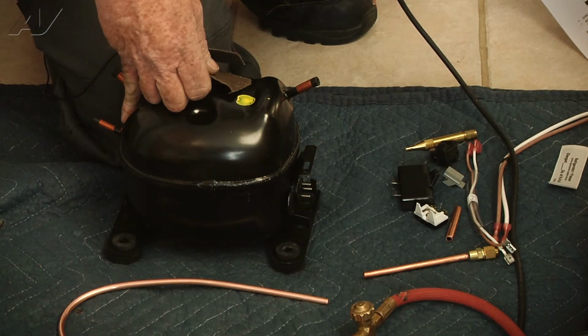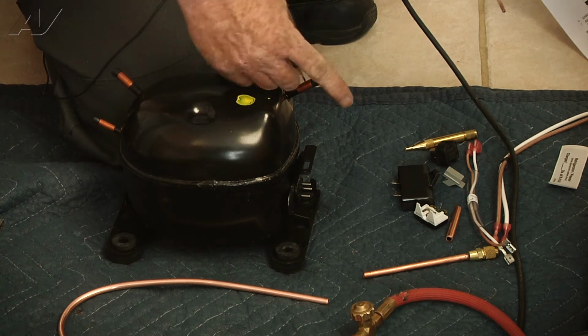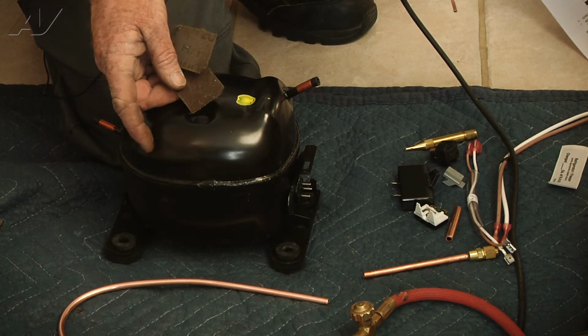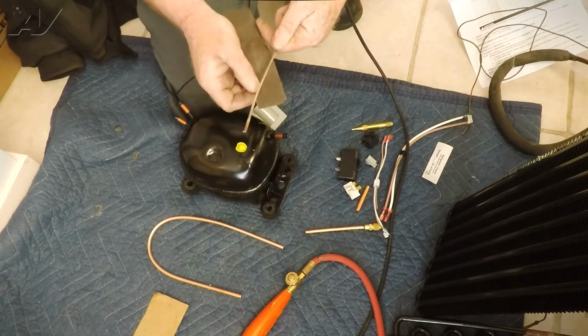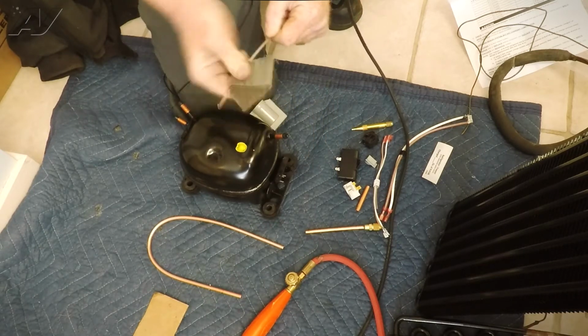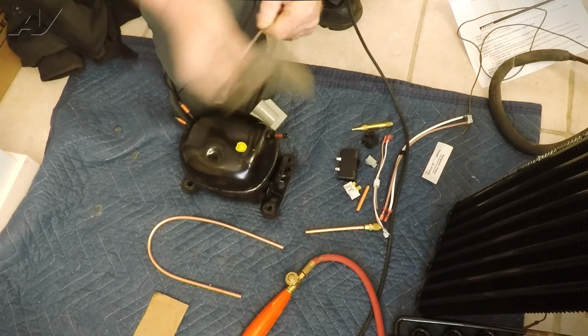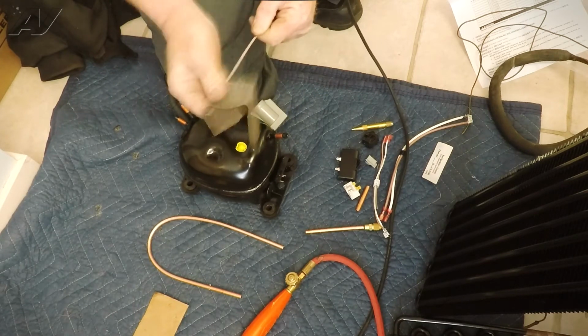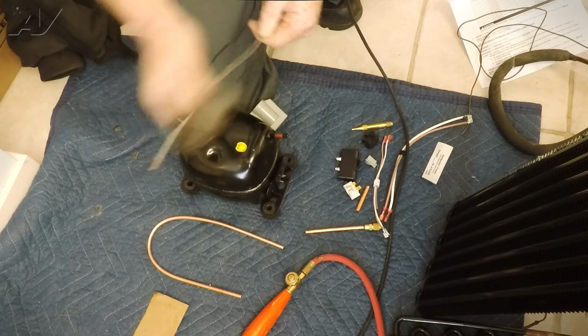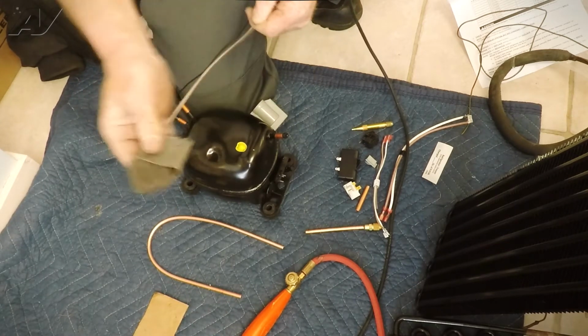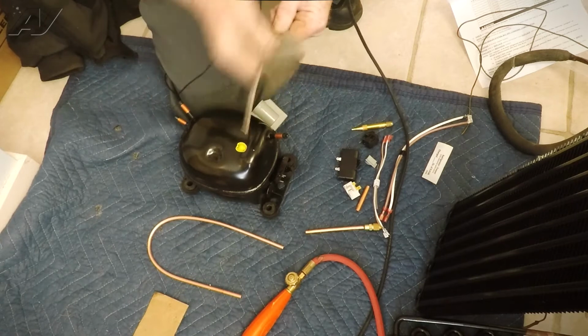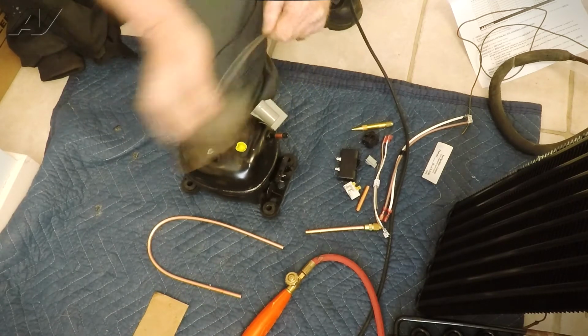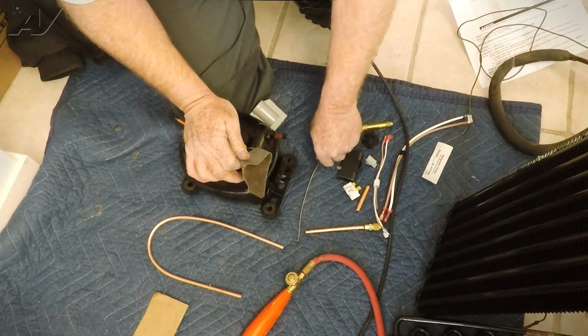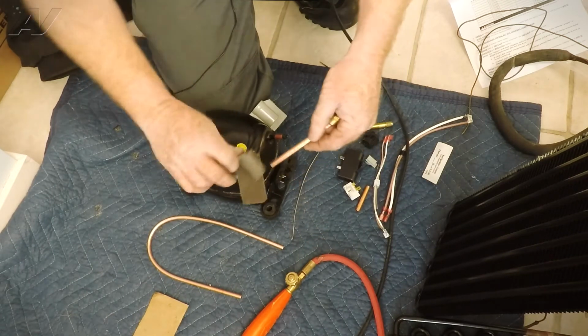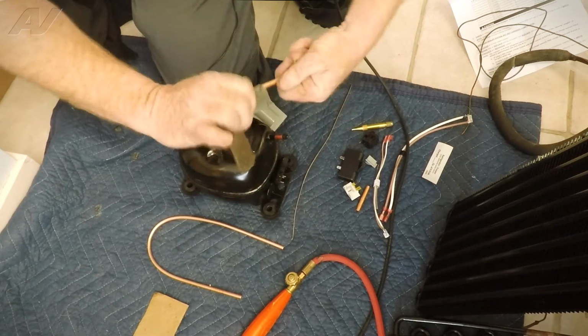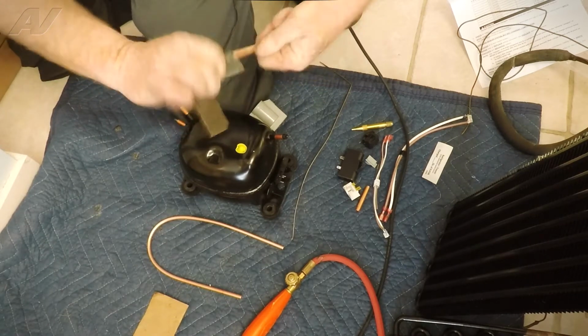Now, we're going to be installing the access valve and the connecting tubing. So first you want to clean your brazing rod with some sandpaper, just to make sure that if there's any oxidation on it, you get it off. Because just sitting around, they will oxidize. Now with the brazing rod cleaned, we're going to also clean the tubing that's going to be welded.